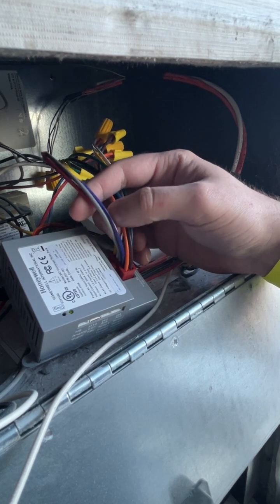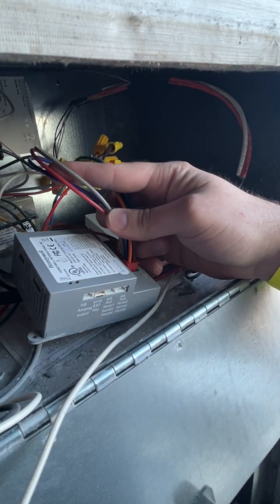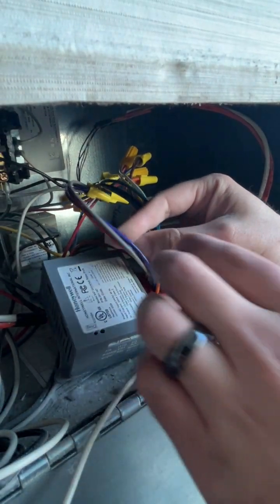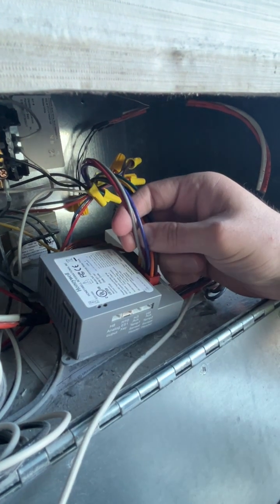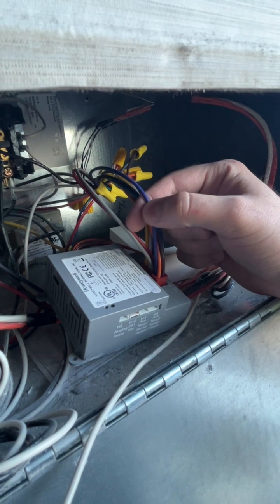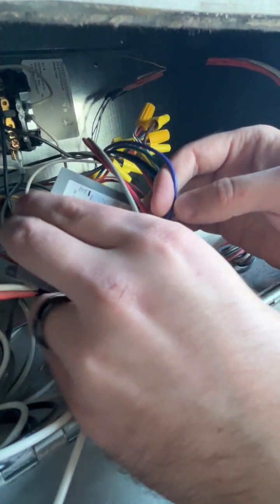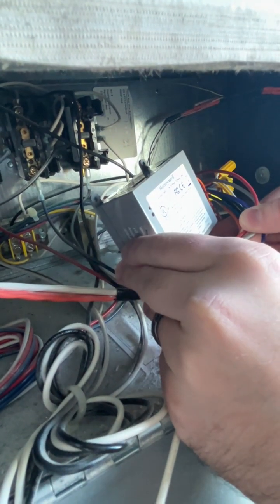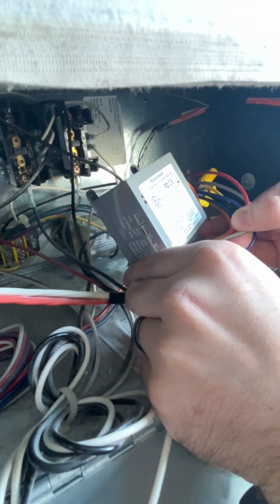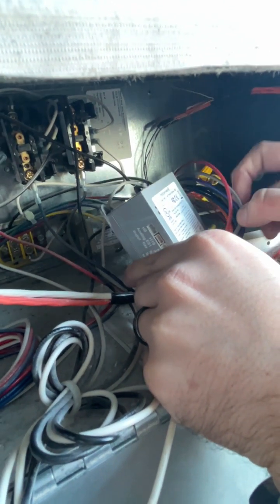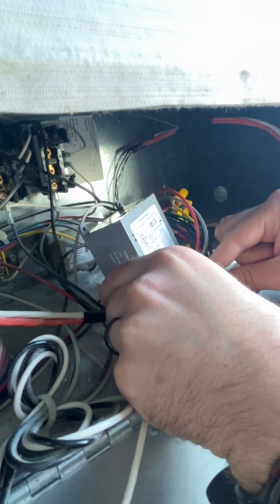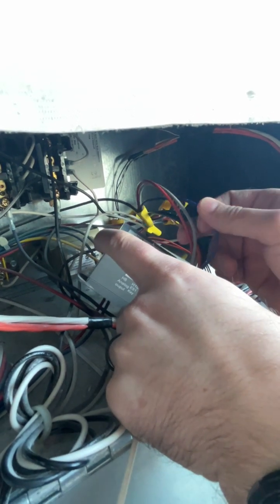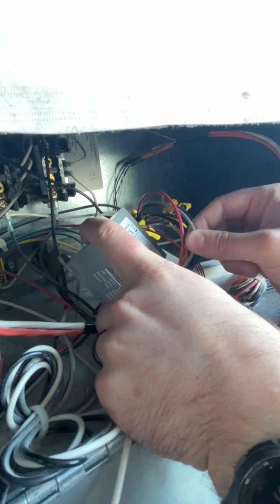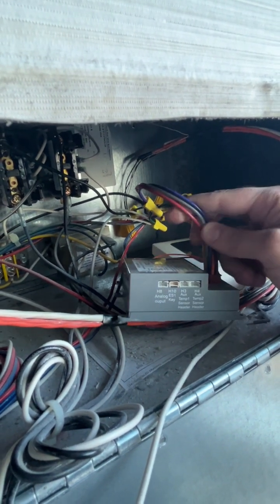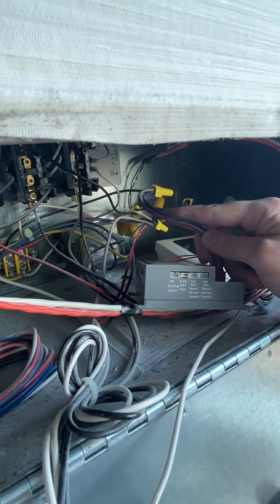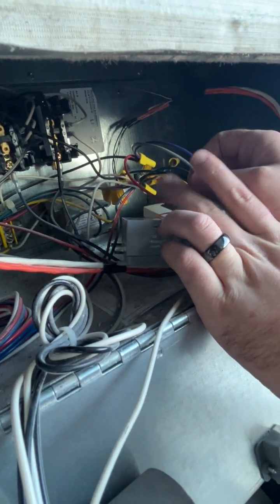Gray, violet, and red all need to be connected to the 24 volt AC power. These are just for different relays, like for your actuators. For the three fan relays, your fan common is purple or violet. Then your valve common is gray. So that's just what's feeding those relays. In this case, they're all fed 24 volt AC, so they should all be tied together. And red is just your power to the unit itself.